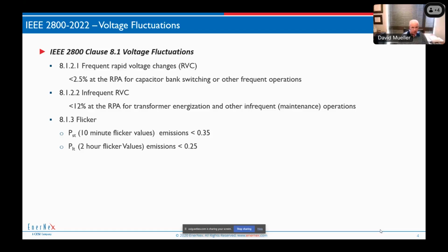The flicker meter should probably be different in the way that it senses flicker, but as of right now, what we still have in the industry are these limits based on 60-watt incandescent bulbs. We've got both 10-minute values, the so-called short-term flicker, and 2-hour values. Generally speaking, we like the values to be less than 1.0 per unit on the flicker scale. So at 1.0, we're saying people are going to start to notice the lights flicker, and we want to keep it below that. And so the planning limit for transmission systems is generally 0.8 or 0.6, depending on voltage levels. We're not going to allow a plant to use that whole limit.